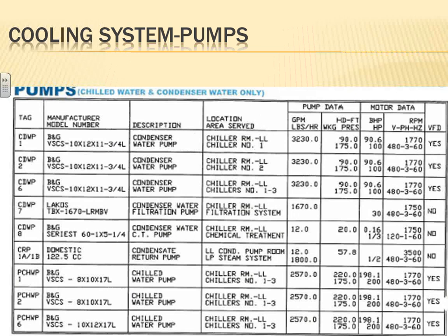If you don't see these pumps, where are the pumps? Especially if they were green designers, like I used to be at one time, and/or engineers, and they missed something. Any comments, guys, about these pumps? That's all pumps. When we size these pumps, you don't go to Article 440, you go to Article 430 and treat them like any other motor. They're nothing but motors.